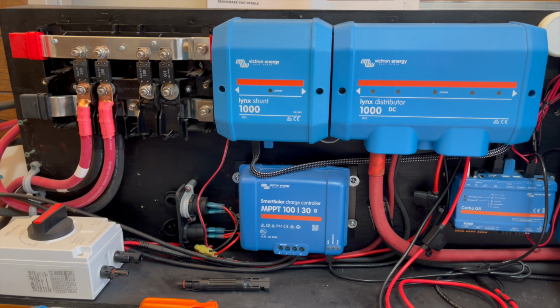It minimizes how often the BMS is stopping a flow or not stopping a flow, depending on whether you're discharging or charging. And when I was charging back up, as I approached the absorption voltage, they all went roughly within a matter of several seconds into absorption mode. Perfect. This is the way I want it.